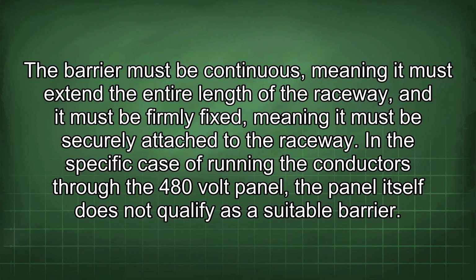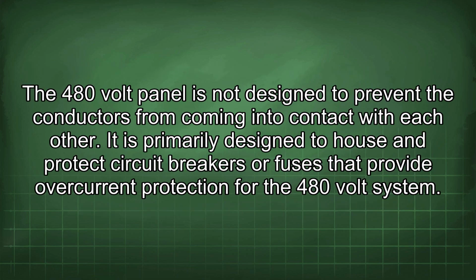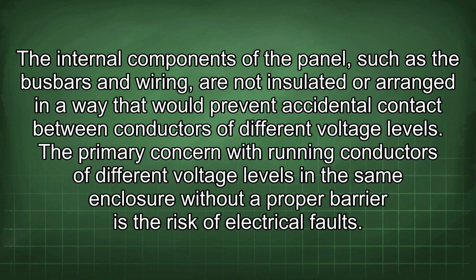In the specific case of running the conductors through the 480 volt panel, the panel itself does not qualify as a suitable barrier. The 480 volt panel is not designed to prevent the conductors from coming into contact with each other. It is primarily designed to house and protect circuit breakers or fuses that provide overcurrent protection for the 480 volt system. The internal components of the panel, such as the busbars and wiring, are not insulated or arranged in a way that would prevent accidental contact between conductors of different voltage levels.